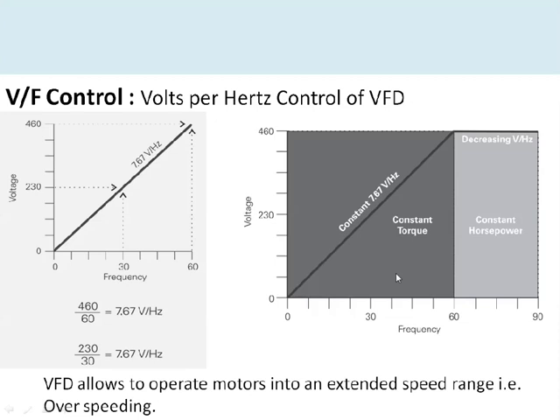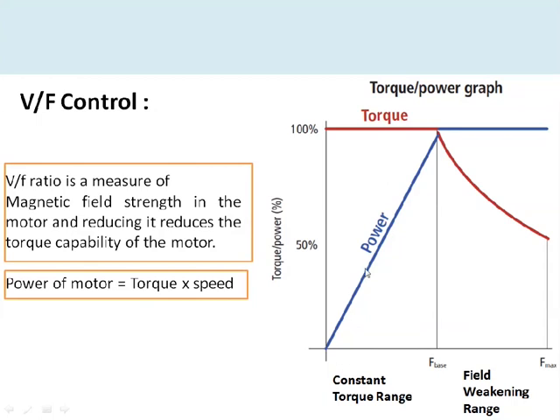Above the base speed, increasing frequency increases motor speed, but the torque decreases. Since power equals speed times torque, and as speed increases while torque decreases, the power remains constant — this region is therefore called the constant power region. The VFD allows motors to operate in an extended speed range above the rated base frequency, which is not possible without a VFD. Above base speed, the V/F ratio decreases, causing flux to decrease and therefore torque to decrease as well.